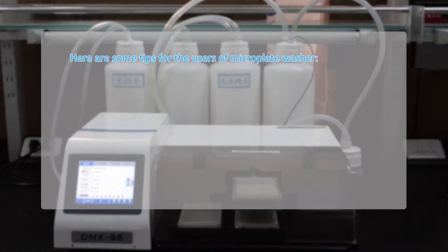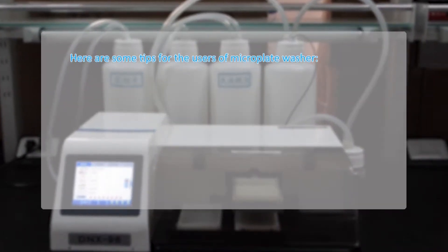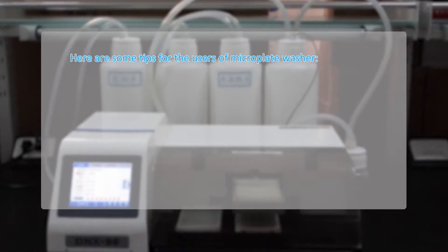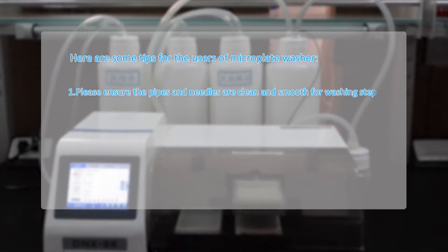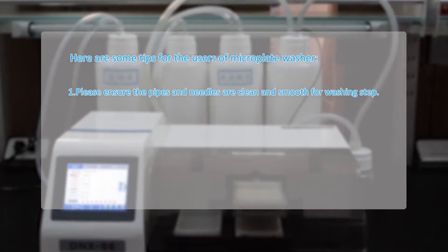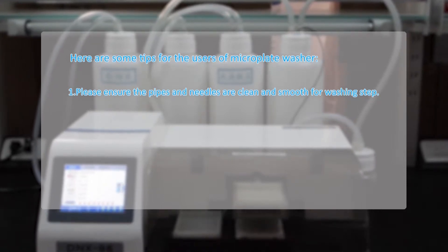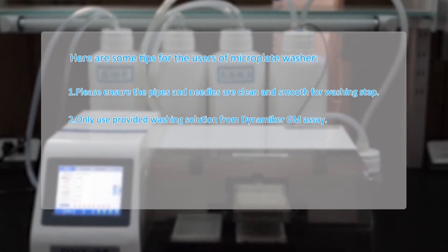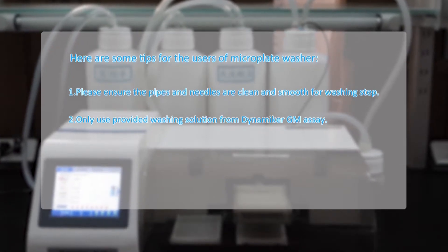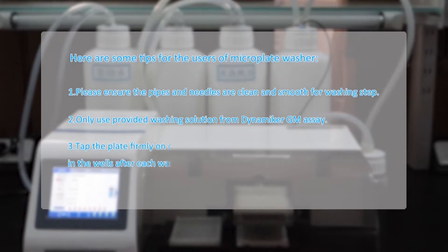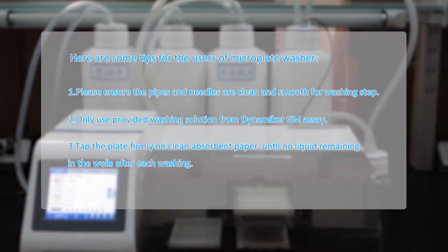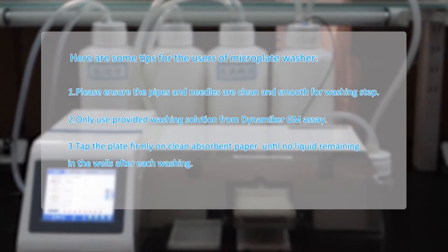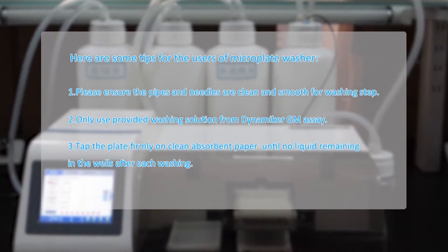Here are some tips for the users of microplate washer. First, please ensure that the pipes and needles are clean and smooth for washing step. Second, only use provided washing solution from Dynamiker GM assay. Third, tap the plate firmly on clean absorbent paper until no liquid remaining in the wells after each washing.